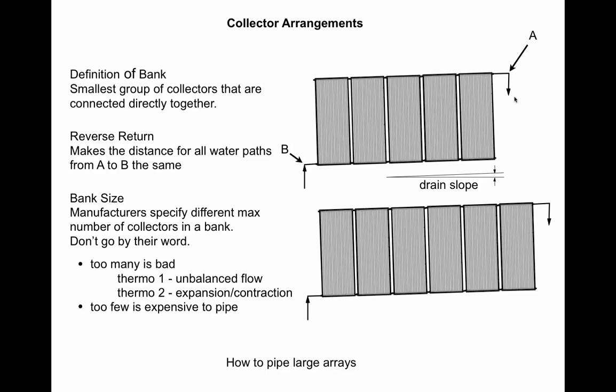Now let's go through collector arrangements. We define a bank as a group of collectors soldered directly to each other. The top drawing shows five collectors with B as the low point and A as the high point — this is called a reverse return: you go in lower left and come out upper right. If you follow a molecule of water from B to A through any possible path in any collector, all geometric path lengths are identical. That's what reverse return achieves — it helps balance the collectors and gives uniform flow to every one.